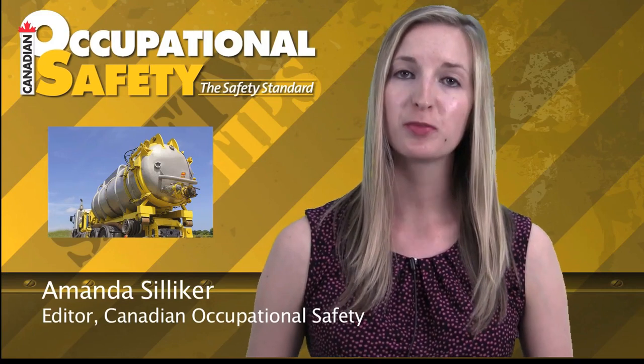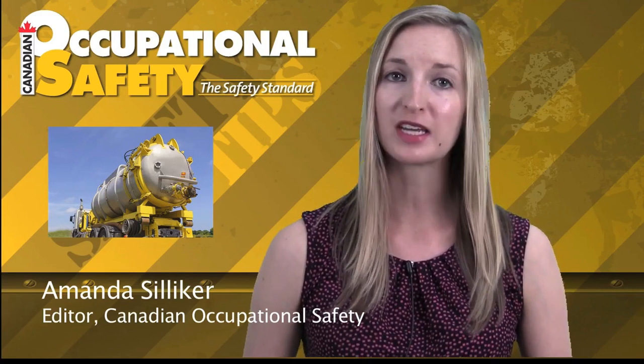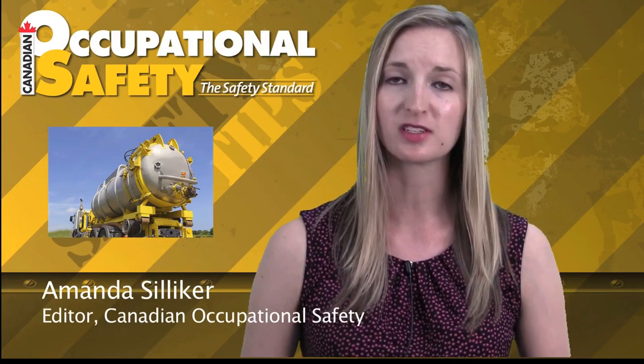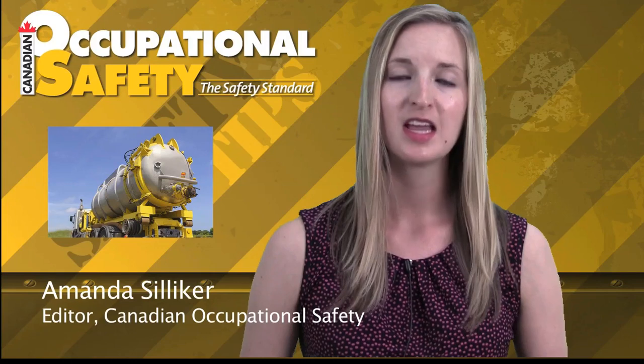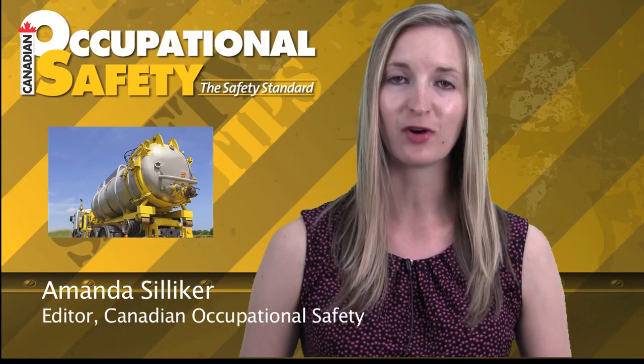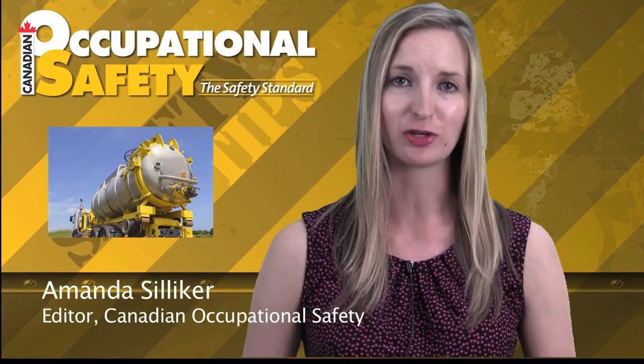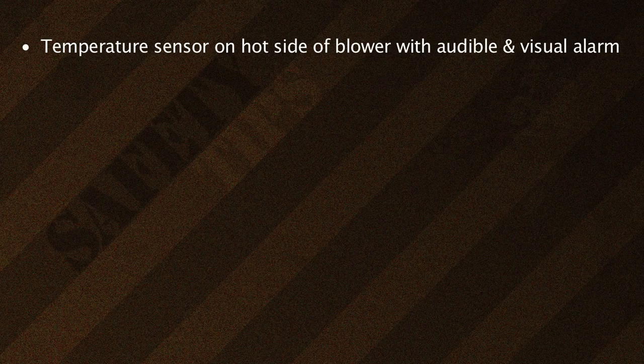According to Enform, the blower and associated rubber hose overheated, and this action ignited the residual hydrocarbons in the blower's associated hose and piping. Consider these safety tips from Enform to prevent a similar incident when operating vacuum trucks containing hydrocarbons. Ensure that a temperature sensor is installed on the hot side of the blower and that the sensor is equipped with an audible and visual alarm.